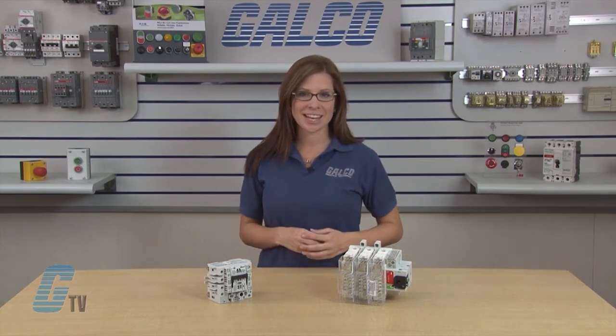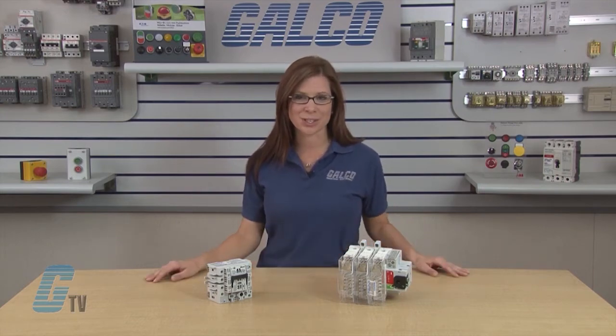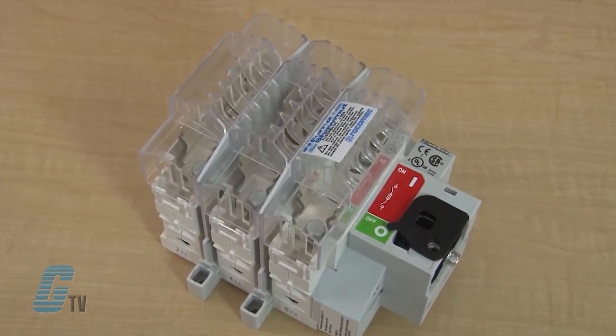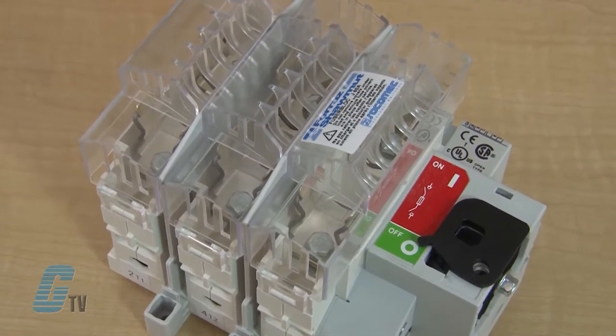FB-Series Disconnect Switches are extremely durable, manually operated fusible disconnect switches. They employ double break contacts per pole that ensure complete isolation of the fuse when the switch is in the off position.